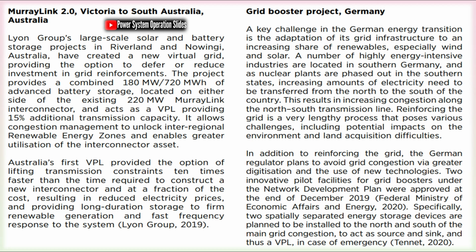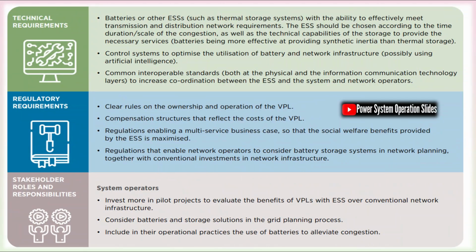DLR-centric VPLs rely on dynamic line ratings plus operational control to temporarily use extra thermal capacity. BESS-fed VPLs strategically locate storage and controllable DERs at boundary nodes to emulate a virtual tie between regions. Practical examples, types of real-world pilots: BESS plus coordinated dispatch.